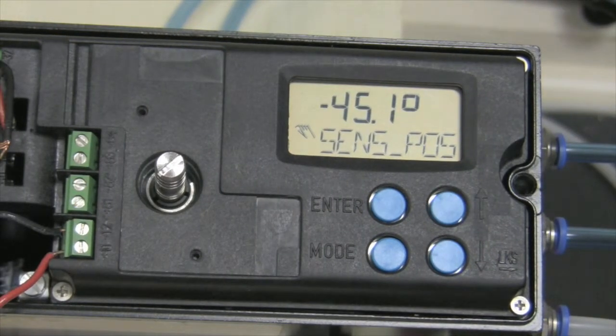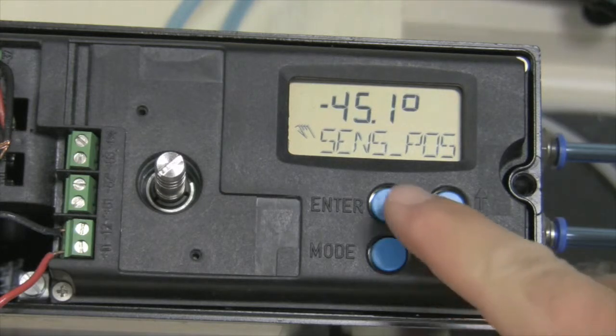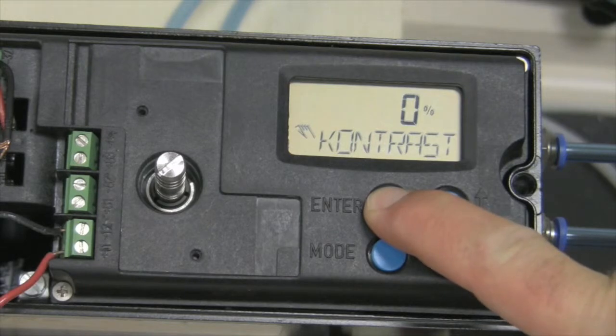To calibrate this positioner, we know that it's on a rotary actuator. So what we will do is press and hold the enter button. We will keep holding it until adjust rot appears.